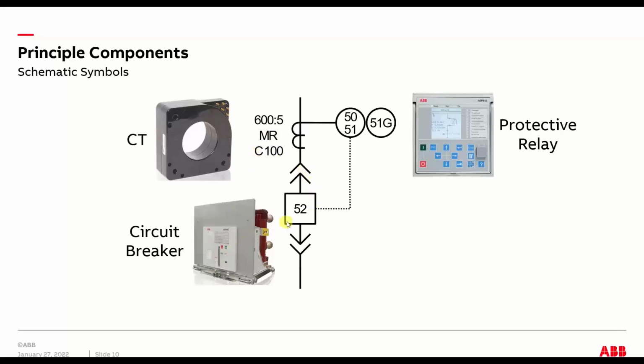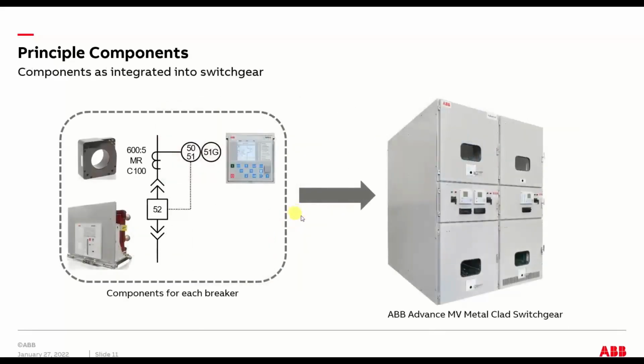And then here's your circuit breaker. Same stuff. This is all pretty much medium voltage gear. And then here are the components that make up one breaker, and then they all go into, in some cases, a bigger assembly. So this is all those components brought into a really short lineup of medium voltage metal clad gear. And this is a double stack, so this is actually 4 breakers, 2 on top, 2 on the bottom.